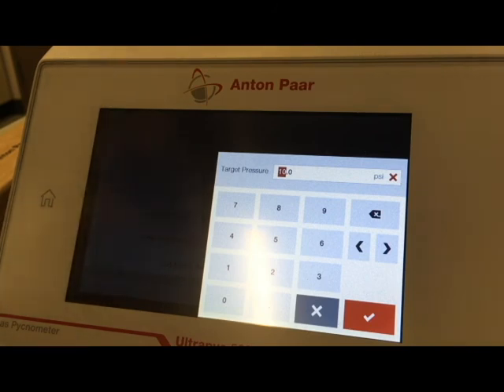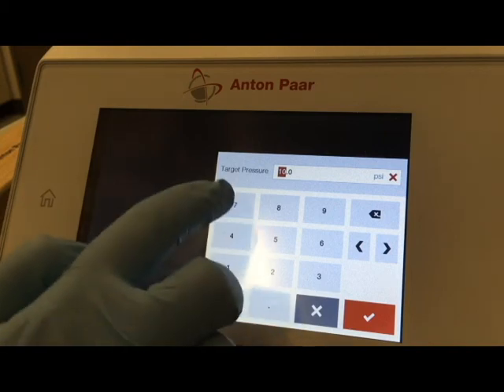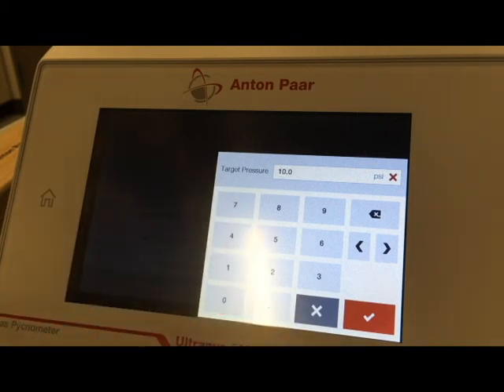If you have a monolith, meaning a solid sample, you want to use about 18 psi. If you have a powder, you want to use about 10 psi. If you have a brittle or a biological sample, you want to use 4 psi. If you're using the micro, meso, or nano cells, you want to use 10 psi or less, since they are not able to withstand larger pressures. For us today, we're going to be doing a powder, so we're going to do 10 psi right here.